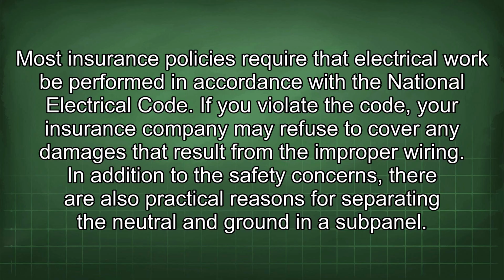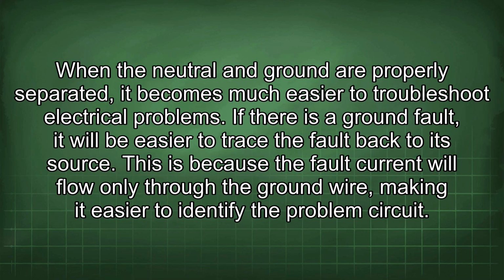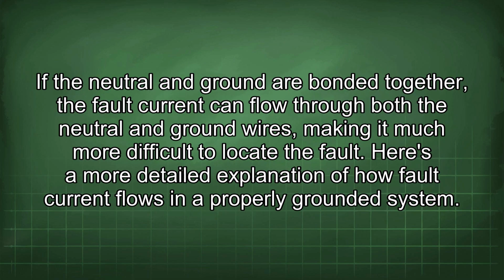In addition to the safety concerns, there are also practical reasons for separating the neutral and ground in a subpanel. When the neutral and ground are properly separated, it becomes much easier to troubleshoot electrical problems. If there is a ground fault, it will be easier to trace the fault back to its source. This is because the fault current will flow only through the ground wire, making it easier to identify the problem circuit. If the neutral and ground are bonded together, the fault current can flow through both the neutral and ground wires, making it much more difficult to locate the fault.